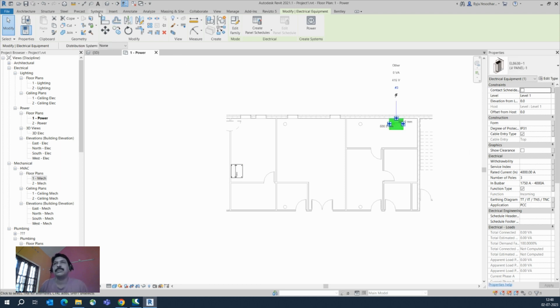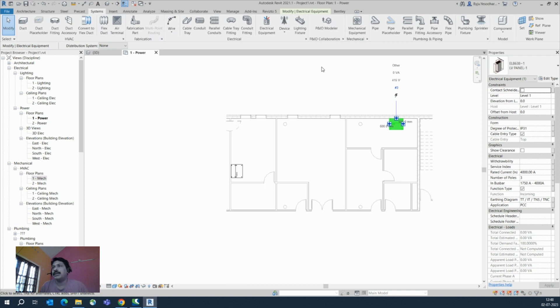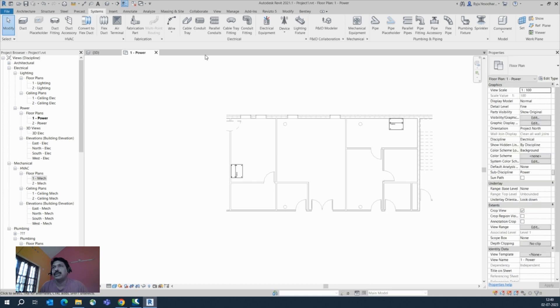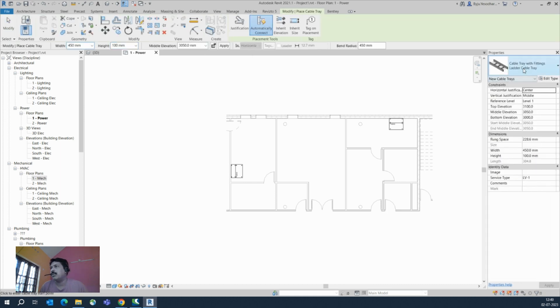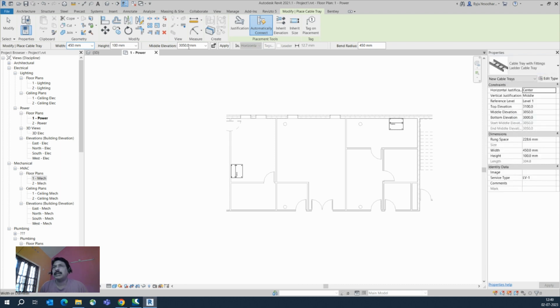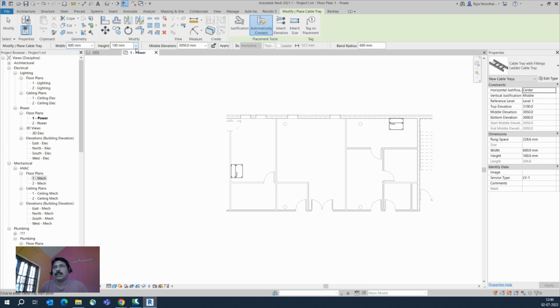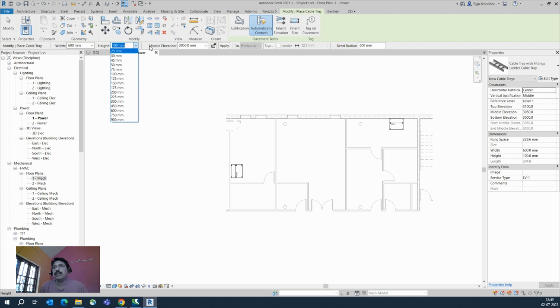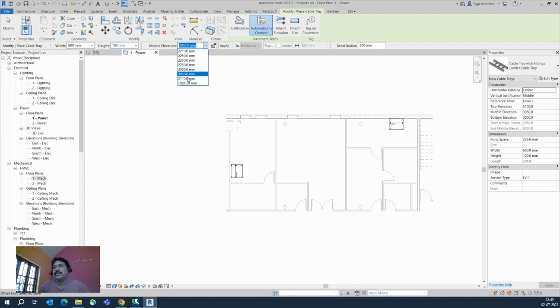I'll go to the System tab again and choose cable ladder or cable tray. Just click on cable tray and from the Properties bar you can get all the cable trays and cable ladders. I'm using cable ladder first. You can see the available details — choose the size and height of the cable tray. I'm choosing 100 for the height. You can also set which level the cable tray runs at; I'm choosing elevation 3050.